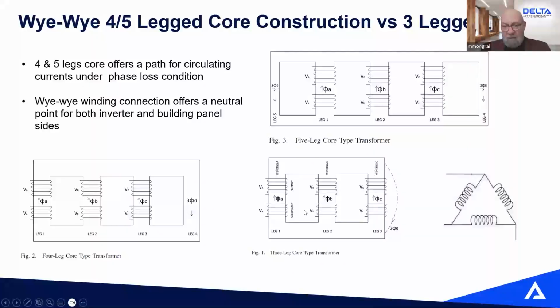But since you have magnetic flux going through, there's still going to be some voltage on the secondary side of that coil, and the voltage drop might not be enough for the inverter or the system to understand that, oh, I've lost a phase, I need to shut down. So the solution to this is to create a core with a four or a five-legged core to provide another path for that flux to go. So when you lose a phase, instead of just going in those two legs, your flux will have a fourth or a fifth path to go. The result will be that the magnetic field in that leg will be a little bit less. So the residual voltage that you'll see on your secondary winding when you lose this phase will be low enough for the inverter, or the system, to understand that I've lost a phase, I need to shut down. So that's the requirement, which is most of the time demanded or required by the inverter.